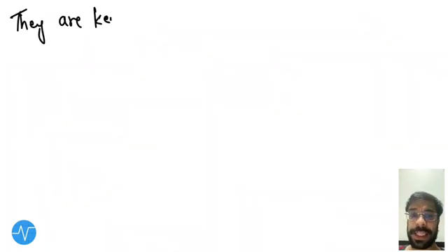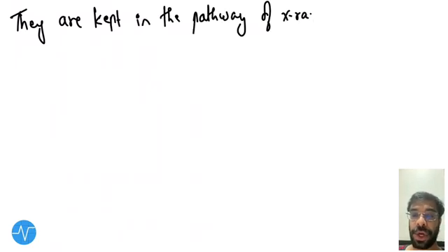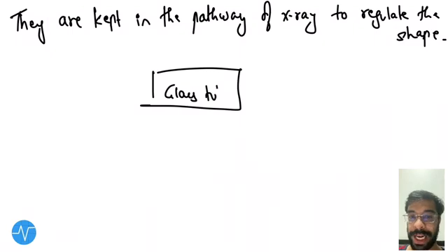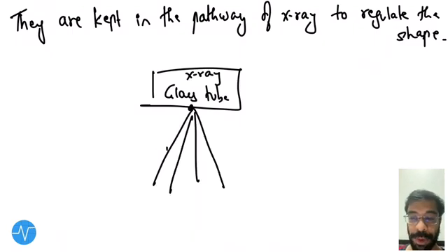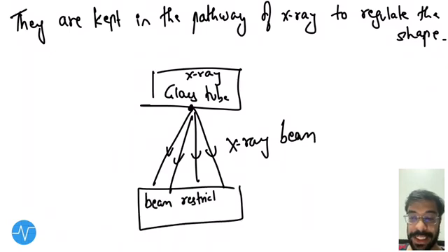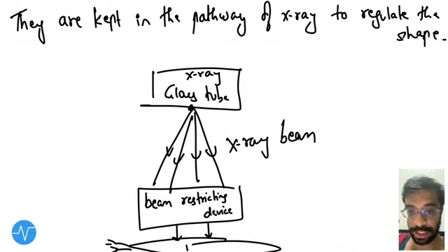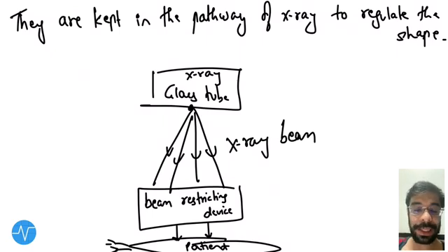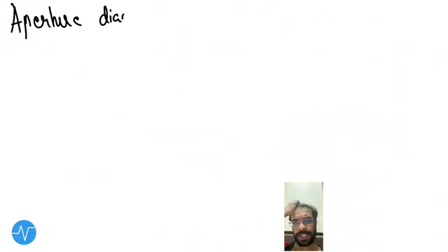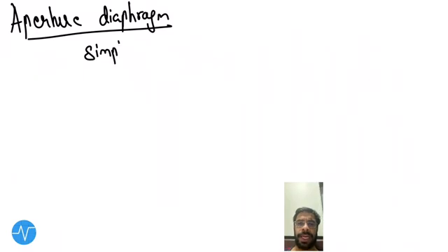Where are they placed? They are kept in the pathway of x-rays to regulate the shape. The x-ray beam is produced from the glass tube, hits the beam restricting device which restricts its shape, and this restricted beam then hits the patient. Therefore, it is kept between the tube and the patient.